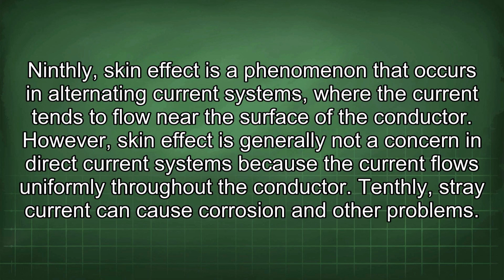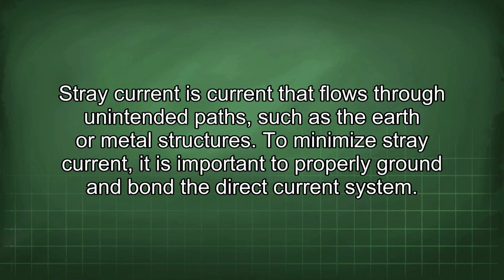objects. Ninthly, skin effect is a phenomenon that occurs in alternating current systems, where the current tends to flow near the surface of the conductor. However, skin effect is generally not a concern in direct current systems because the current flows uniformly throughout the conductor. Tenthly, stray current can cause corrosion and other problems. Stray current is current that flows through unintended paths, such as the earth or metal structures. To minimize stray current, it is important to properly ground and bond the direct current system.